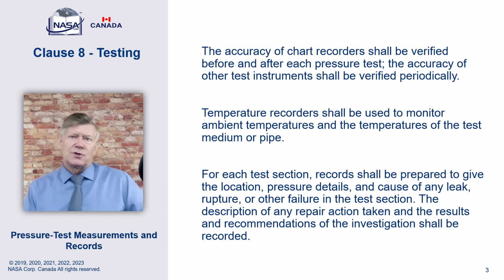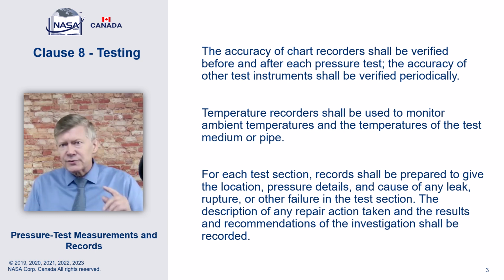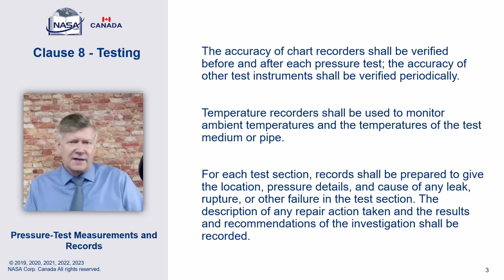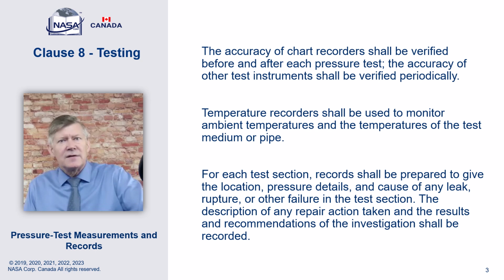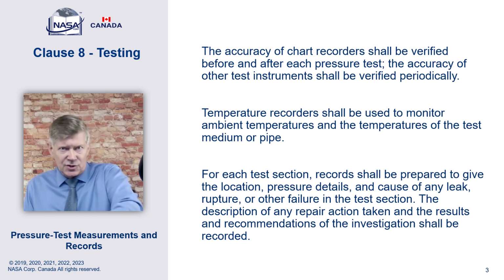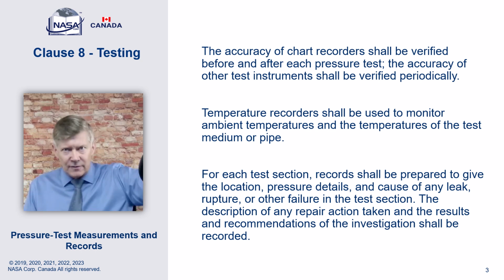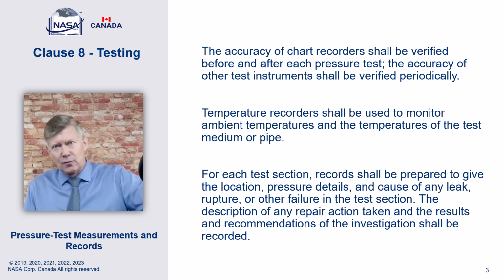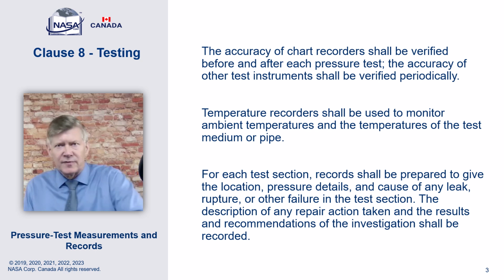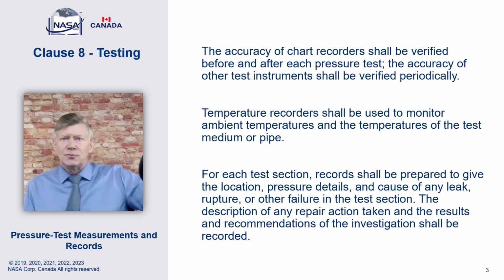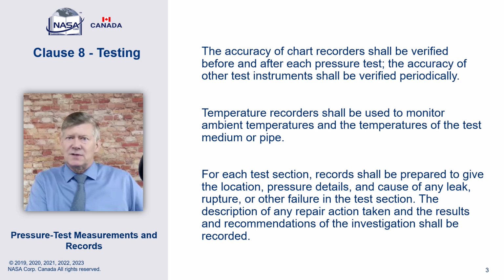the test? So to do a verification, what you'll typically do, you will have a deadweight tester, or you will have a gauge or something calibrated that doesn't leave the shop. Okay, and when it's time to do a test, the equipment you're going to be using in the field, specifically the chart recorders, are verified, right, against your deadweight tester. Then you go out in the field, you do the test, you bring it back, and you check the chart recorders again. Are they still reading accurately? That's what validates your test.